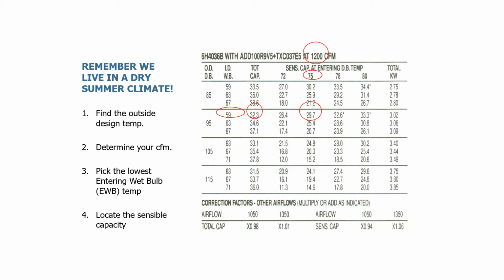This is another way of looking at it. Again, we're going to find the outside temperature. Here, the axis is here. Say we're going to pick on 95 degrees today. Determine your CFM. Notice that they don't give you any CFM; it tells you it's fixed at 1200. You pick the lowest entering wet bulb. We're going to use 59 degrees. Locate the sensible capacity. Here they give you the total, which is 32, and they give you the sensible capacity, which is 29. So this is a 3-ton machine. And they're telling you that under these conditions, the sensible capacity is 30,000 BTUs. It's not 36,000 BTUs.